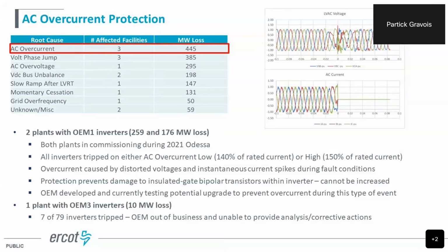There are 2 different levels: a minor, at 140% of rated current, or a high, at 150%. The lower fault allows them to come back online more quickly, after a few seconds, while the high takes about 5 minutes for them to come back on and reset. This protection cannot be increased or disabled. It is designed to protect the IGBTs within the inverter that can be blown with high current. So you cannot increase this protection.